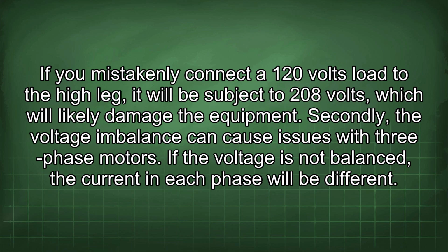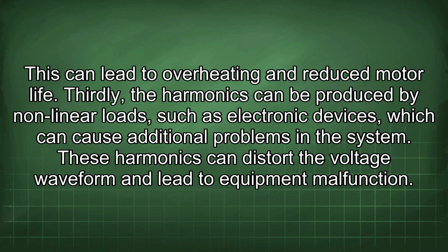Secondly, the voltage imbalance can cause issues with three-phase motors. If the voltage is not balanced, the current in each phase will be different. This can lead to overheating and reduce motor life. Thirdly, harmonics can be produced by nonlinear loads such as electronic devices, which can cause additional problems in the system. These harmonics can distort the voltage waveform and lead to equipment malfunction.